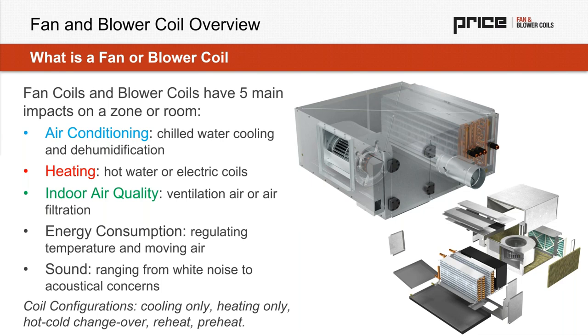We are going to condition air. So a chilled water cooling coil is going to allow for not only sensible cooling and change with temperature, but it's also going to allow for dehumidification. So we're going to have that supply water temperature provided at a temperature below space dew point, which is going to allow that coil to actually condense, and we're going to draw moisture out of the airstream and dehumidify.